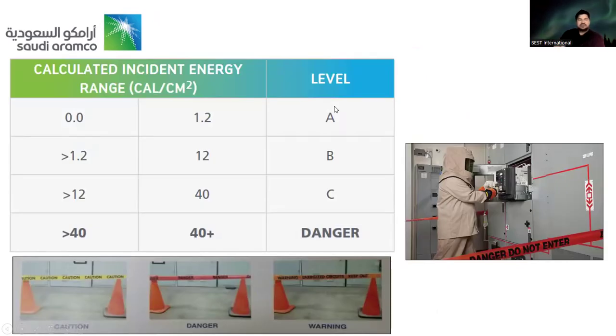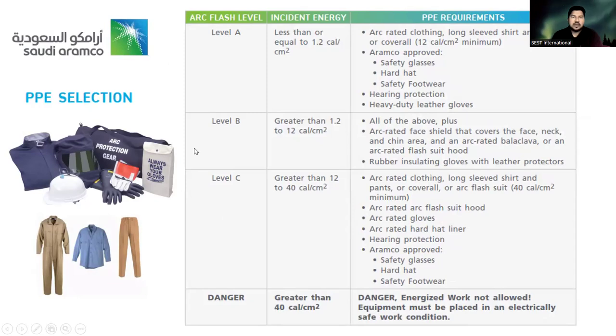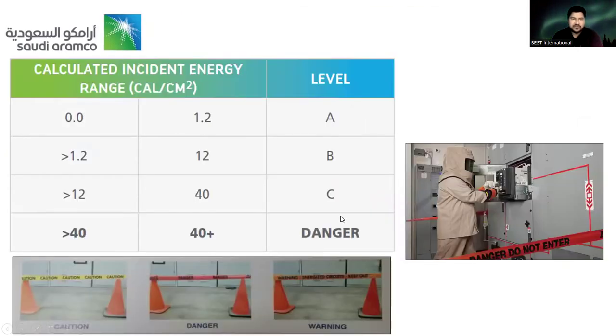Now, calculated incident energy range, calories per square centimeter. There is a level of danger as per the calories per square centimeter, categories A, B, C. Above 40 is critically dangerous. In PPE selection, understand the levels according to A, B, C, according to the calculated incident energy.